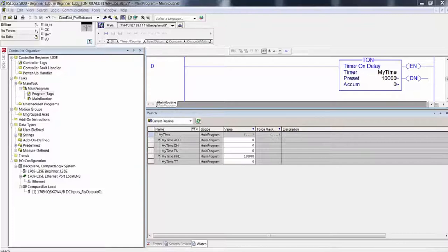Originally, these were relay timers, and when you energized the initiate or start input or screw terminal on this timer relay, it started a timer, and you would set the timer in the older ones with a little knob on front, and it was not very accurate. The accuracy depended on the span or the maximum delay. So if you had a maximum delay of 1 second, then you could probably set it fairly accurately to tenths of a second. If the total possible delay was 10 seconds, then you could probably set it fairly accurately to single second units.